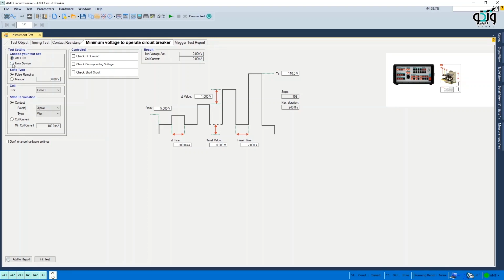In the first step of this test, the equipment to be used in the test is selected from among new device and AMT 105, which is set at AMT 105 by default. And here we proceed without changing it. Then you need to specify whether you are going to perform a closed test or an open test. Note that since some circuit breakers have two open and two closed bobbins, there are open 1 and open 2 as well as closed 1 and closed 2. In this video, we're going to perform the minimum voltage test once for closed mode and once for the open mode.